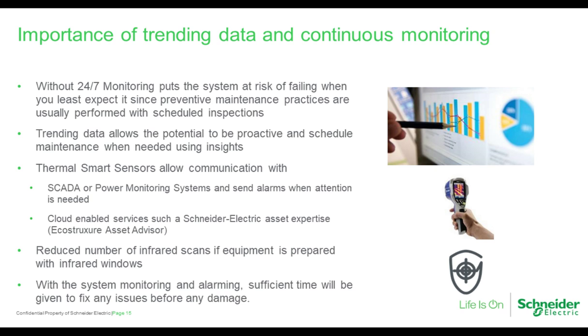And then there's a reduced number of infrared scans of equipment through infrared windows, and also the cost of adding windows. Now you can reduce that cost or not have to add windows because you can use thermal sensors to come back to the system. With system monitoring and alarming, sufficient time will be given to fix any issues before there is extensive damage.